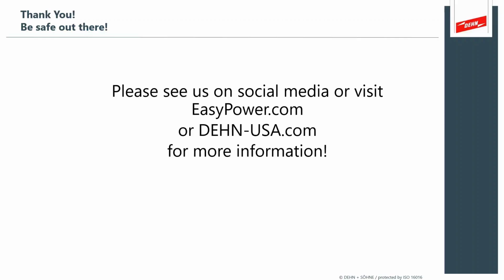So the question from Lionel is, what is the recommended procedure of grounding the shield wire, the drain wire, etc., in low voltage applications? In other words, is it acceptable to bond at both ends or only at one end? And if it is only the one end, which end do you recommend, source or load? So yeah, that is in fact an open issue for troubleshooting right now. I've got a customer in the power industry, and we're tracking that exact issue down. Do you bond both ends?